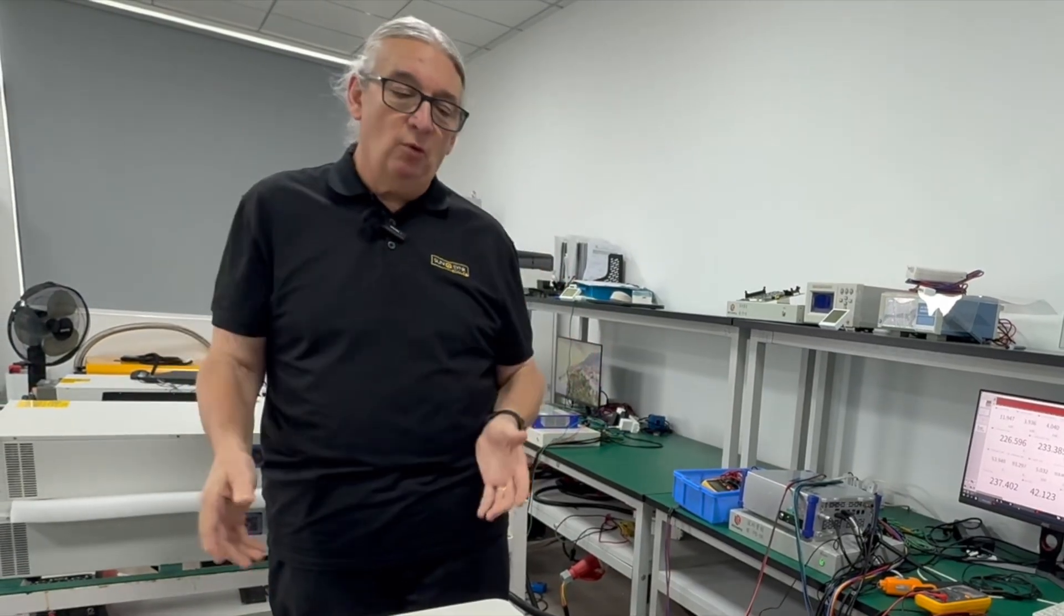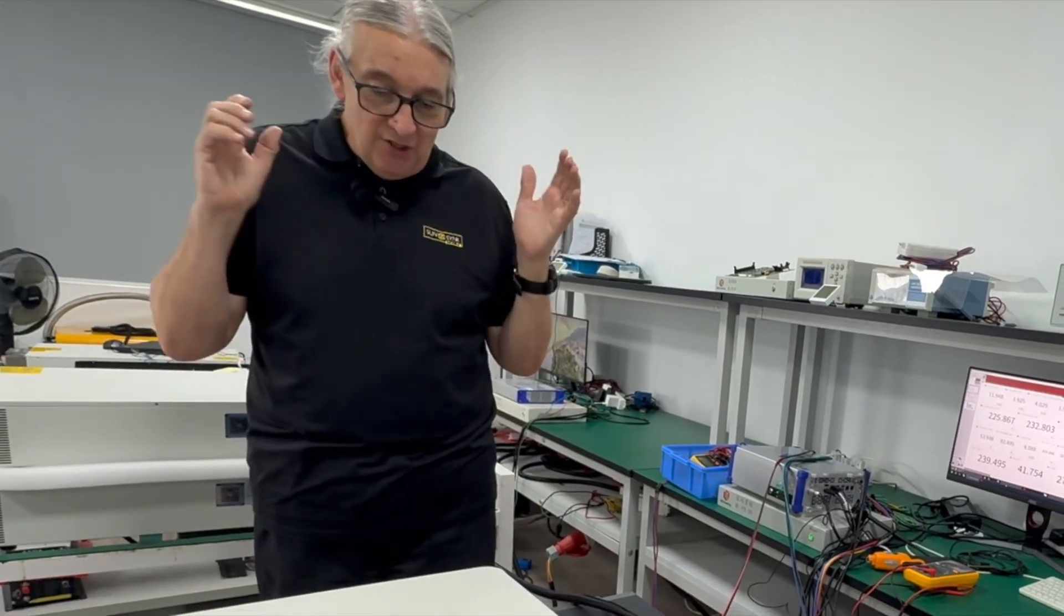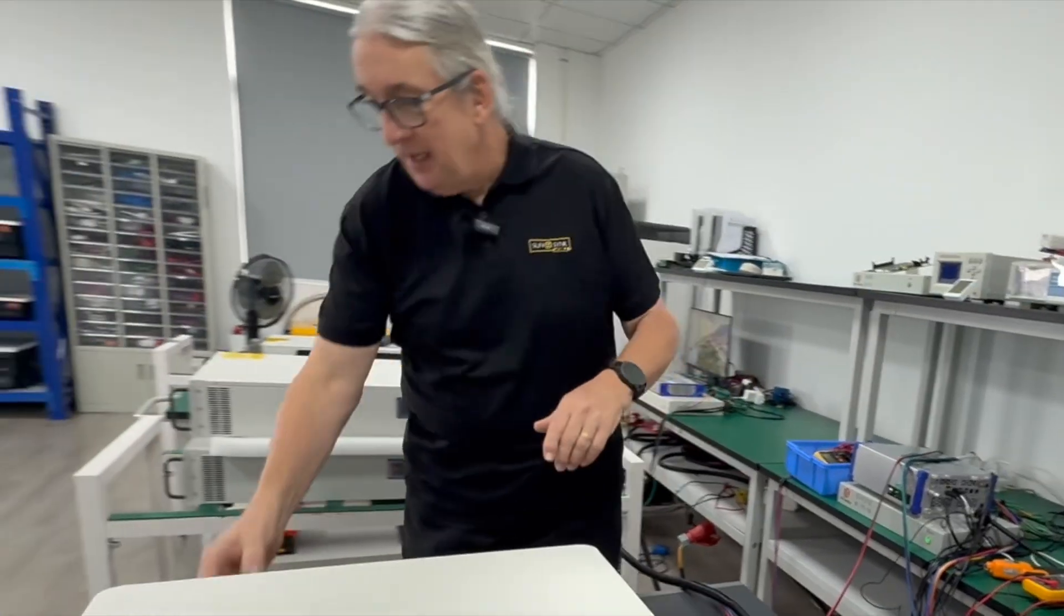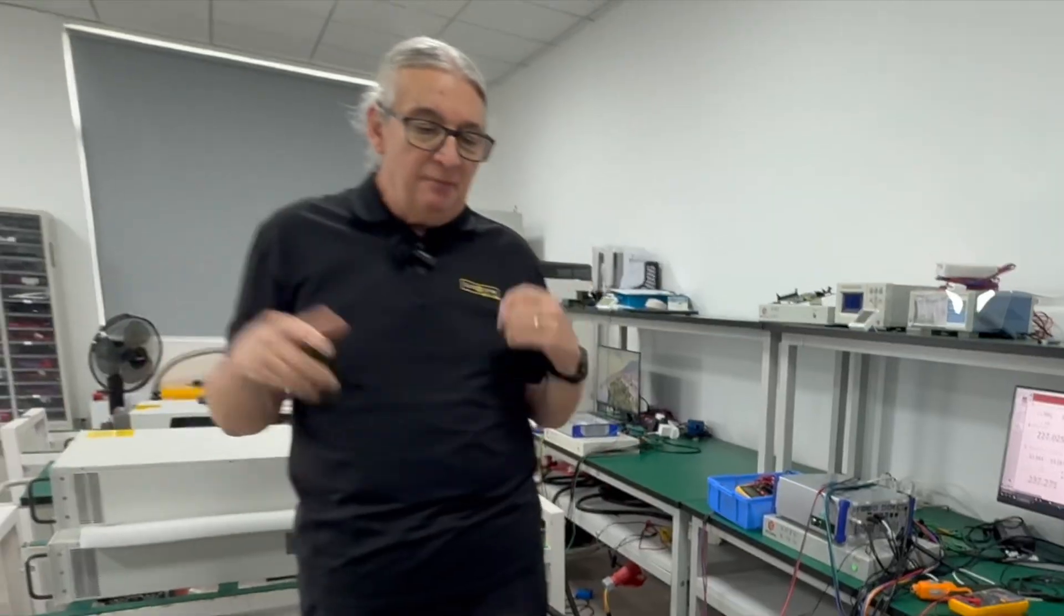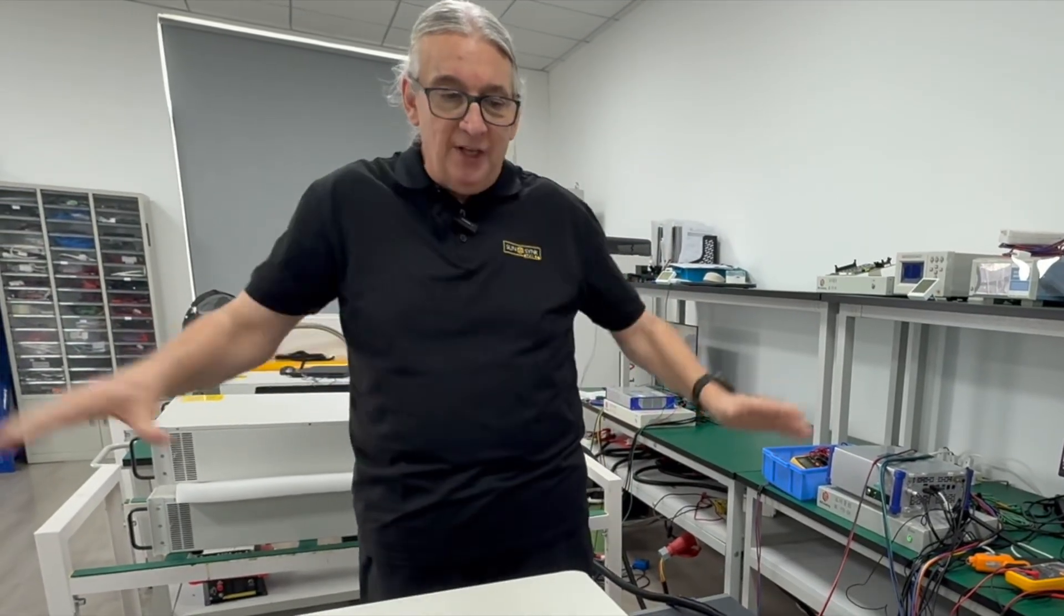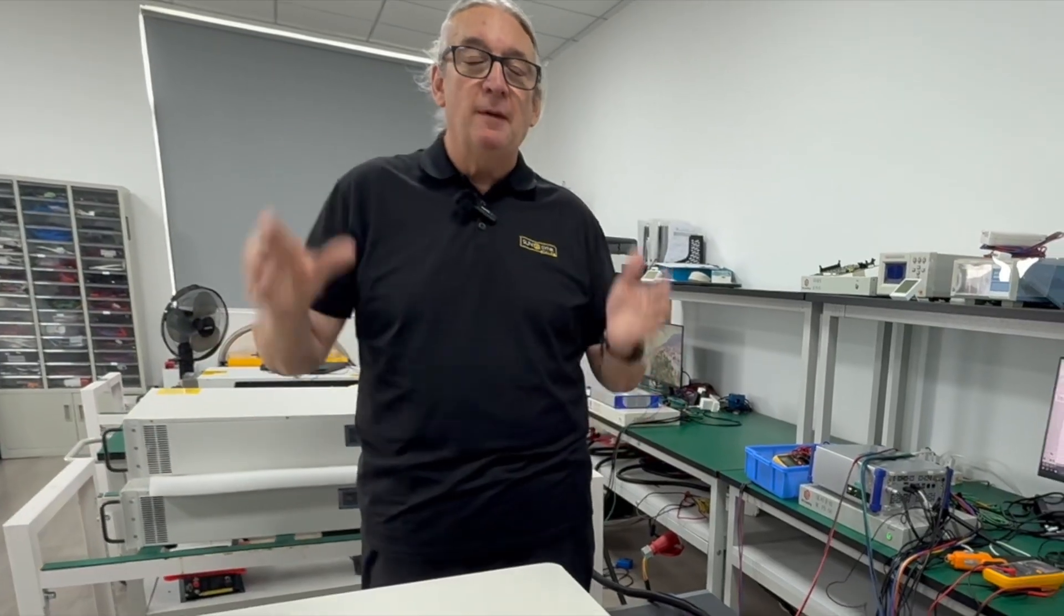This is the 12 kilowatt three phase. It's just going through the testing now. And you see here, there's a whole load of cables. These are using negative temperature coefficient thermistors. These are actually used for monitoring the temperature of all the internal components. And this thing is running absolutely stone cold.